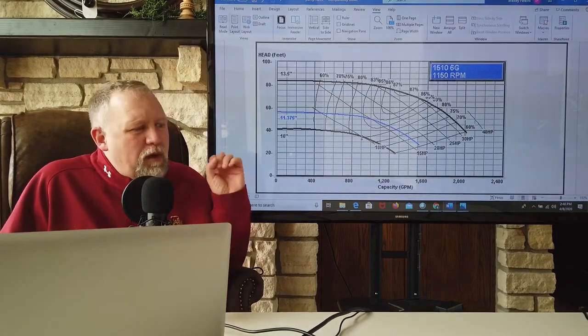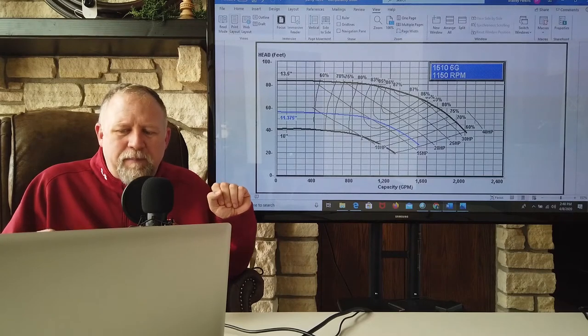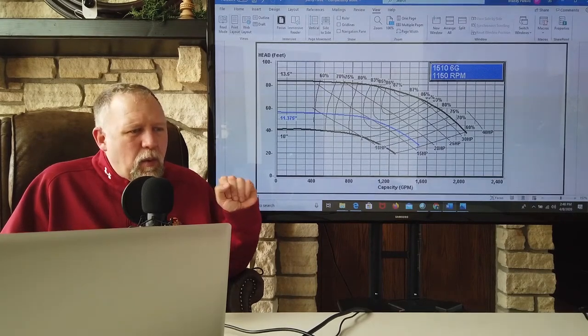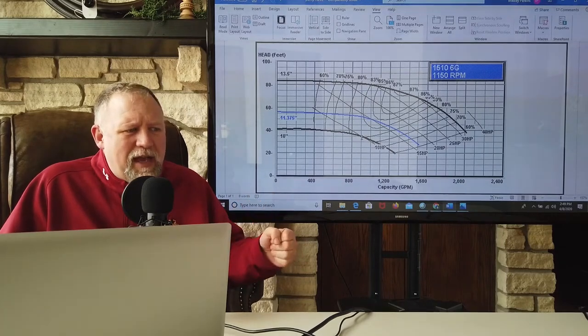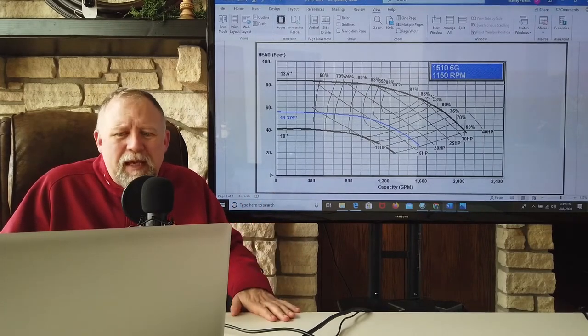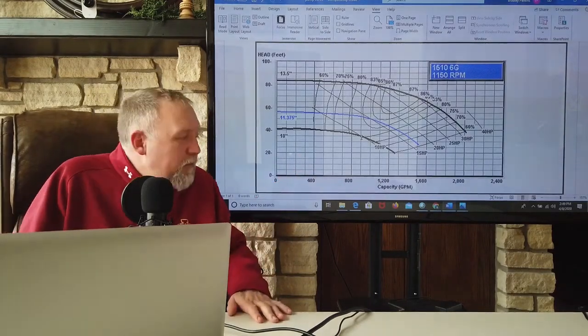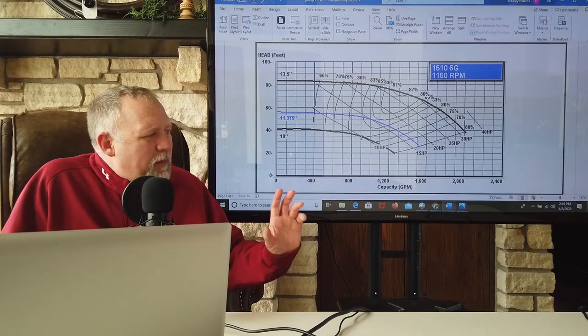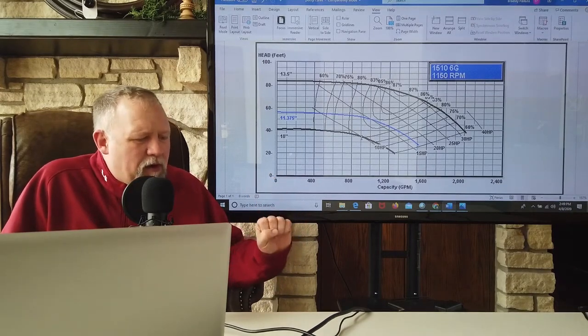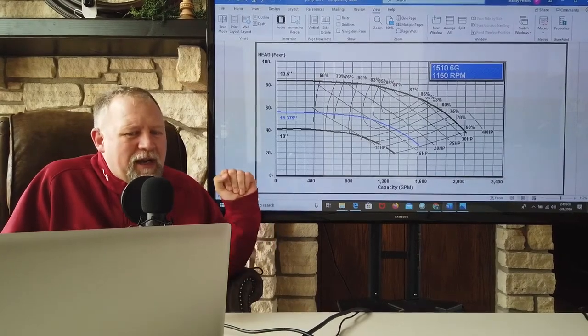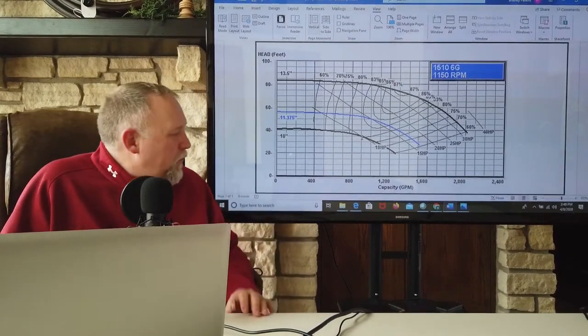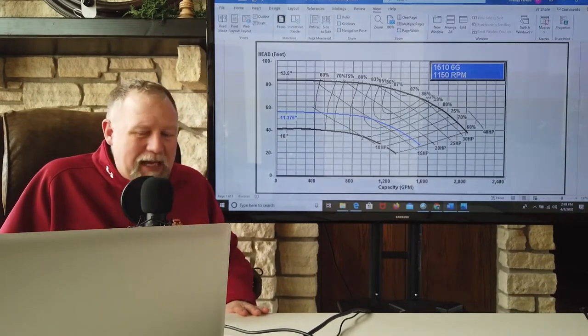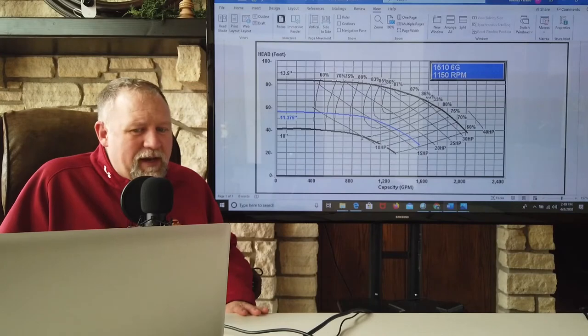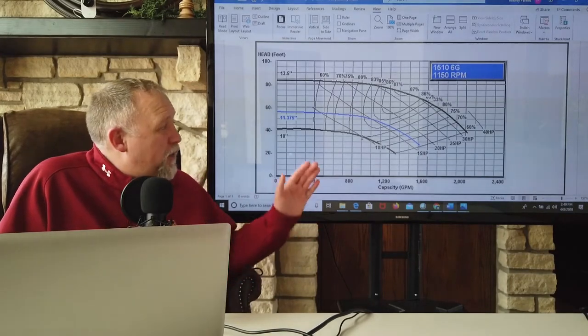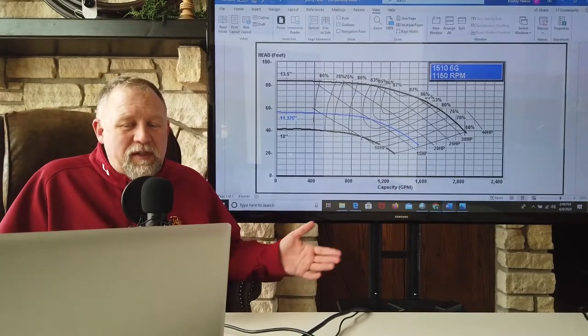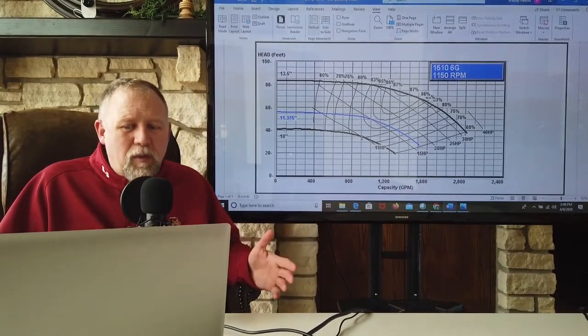Think of it this way. It's kind of like if we had a hose bib, and we weren't sure about the hose size that they were going to connect to that hose bib. Maybe it could be a 1-inch hose, maybe it could be a 2-inch hose, like a fire hose. We say, well, I don't know what it's going to be, so I'm going to estimate a smaller hose with greater pressure loss to make sure that I've got enough pressure there to get water through the system. If that's the case, but you actually put a bigger hose on there, it's going to have less resistance to flow, so you're going to get more flow through that. If we're designing a boiler system, hey, that's not the worst thing that could happen, extra flow rate.